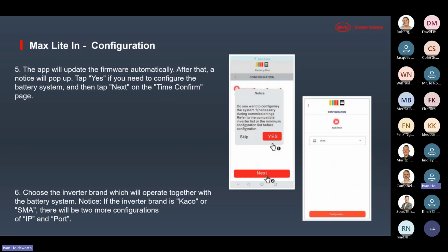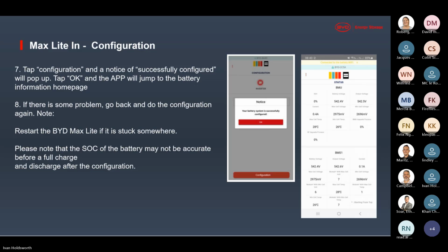And then once you've connected and updated the firmware, you'll have the option of commissioning. There'll be 2 steps in the commissioning. If you click yes, you'll be able to set the time, and you'll also be able to select the inverter brand. It's very important to select the inverter brand. It won't be possible for the battery to operate if the inverter brand isn't correctly selected. And then once your battery has been successfully configured, you'll get your summary screen.